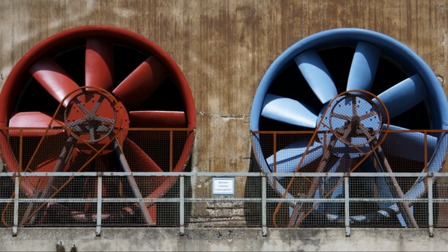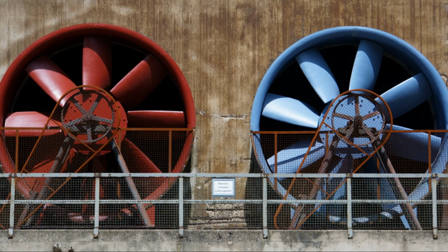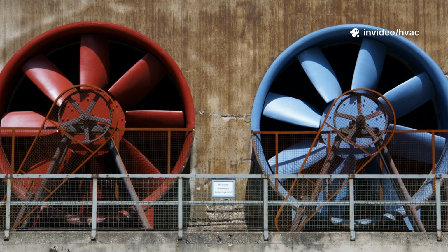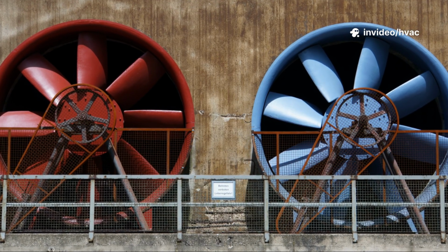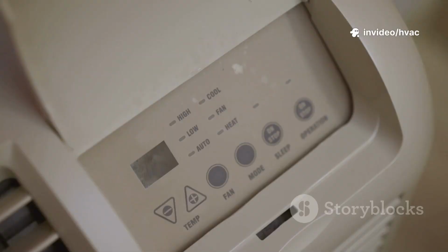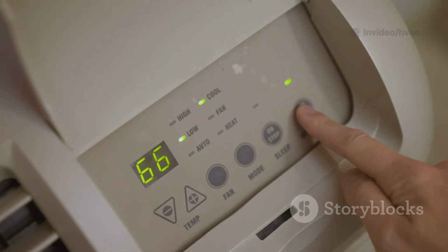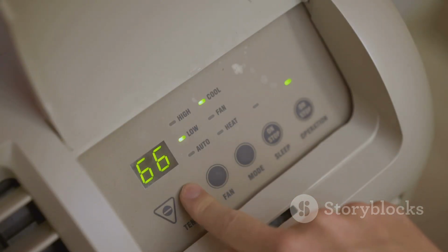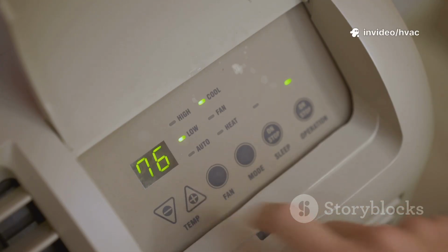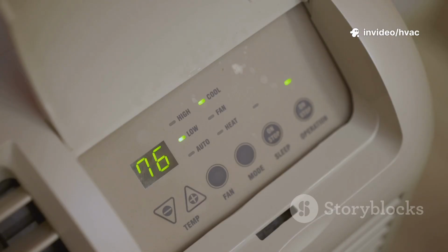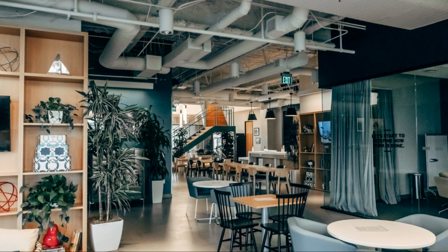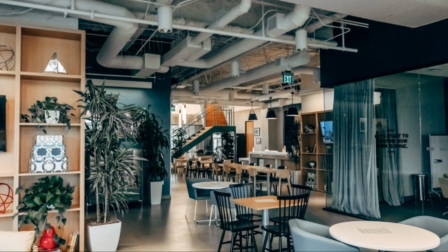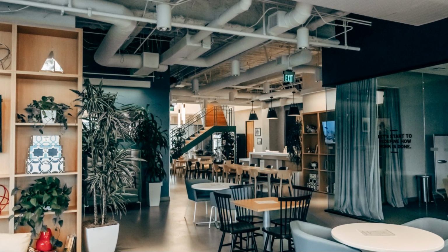This boost increases the airflow, restoring the pressure in the ducts and ensuring that every zone, no matter how sunny or crowded, gets the right amount of cool air. As the rooms cool down and the thermostats sense that the temperature is back to normal, the VAV dampers begin to close. This causes the duct pressure to rise again, and the VFD automatically slows the fan, reducing energy use and preventing unnecessary cooling. This entire process happens quietly and seamlessly, without anyone in the office even noticing.